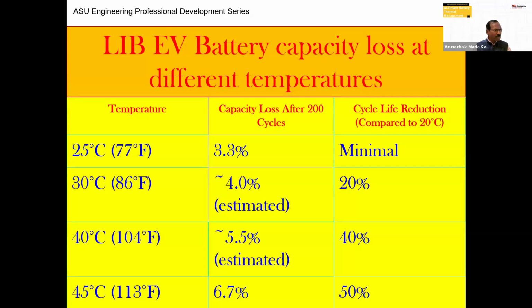However, if you go to 30 degrees Celsius, or 86 degrees Fahrenheit, the loss in capacity is about 4%, sometimes even slightly higher. That translates to almost 20% cycle life reduction compared with 20 degrees.